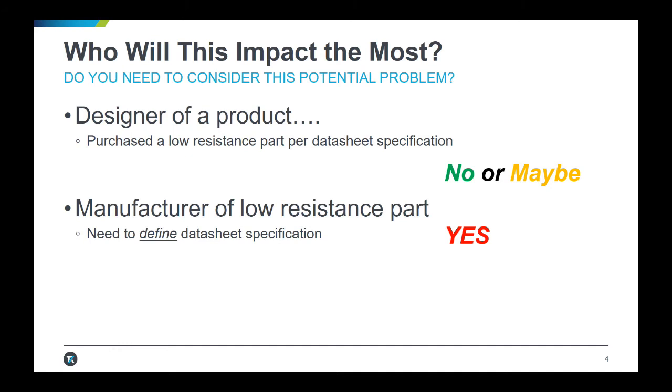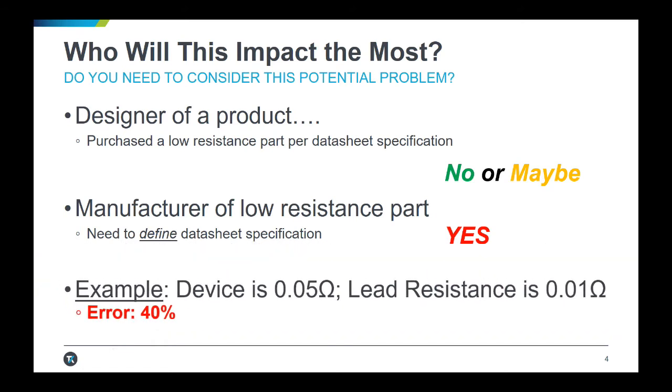If you manufacture low resistance devices and need to guarantee that they meet the specifications you will be providing to potential customers, then obtaining the most accurate measurement of your device is imperative. Consider the situation where you are making 50 milliohm resistors and your test setup uses leads that are 10 milliohms each. This has the potential to result in 40 percent error in what you are measuring.